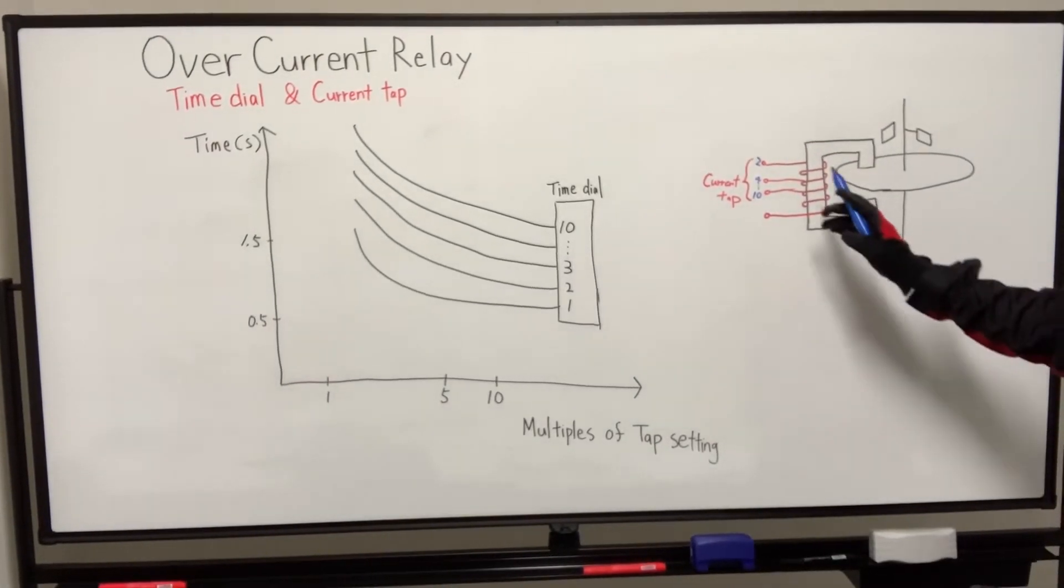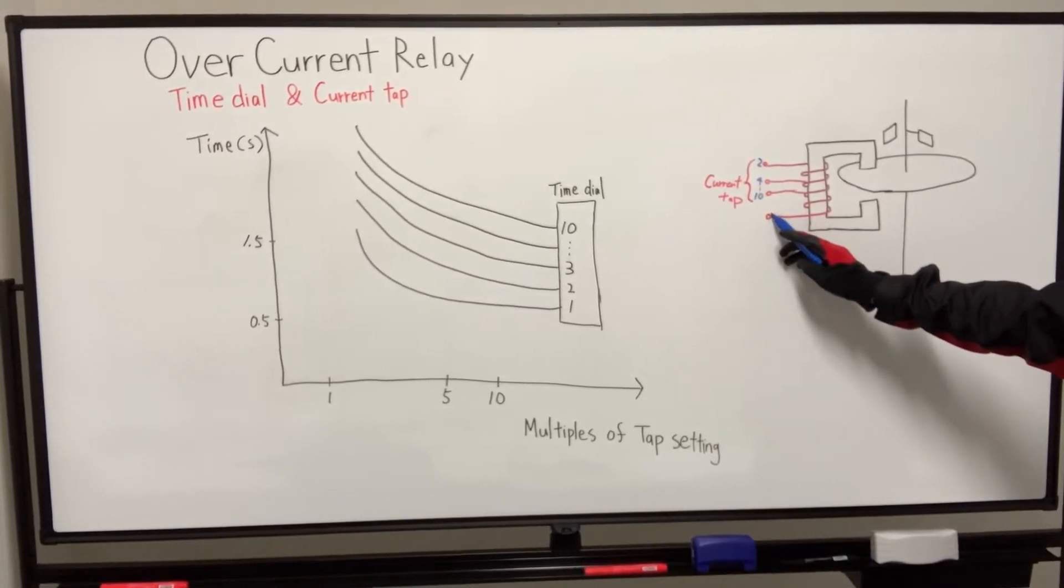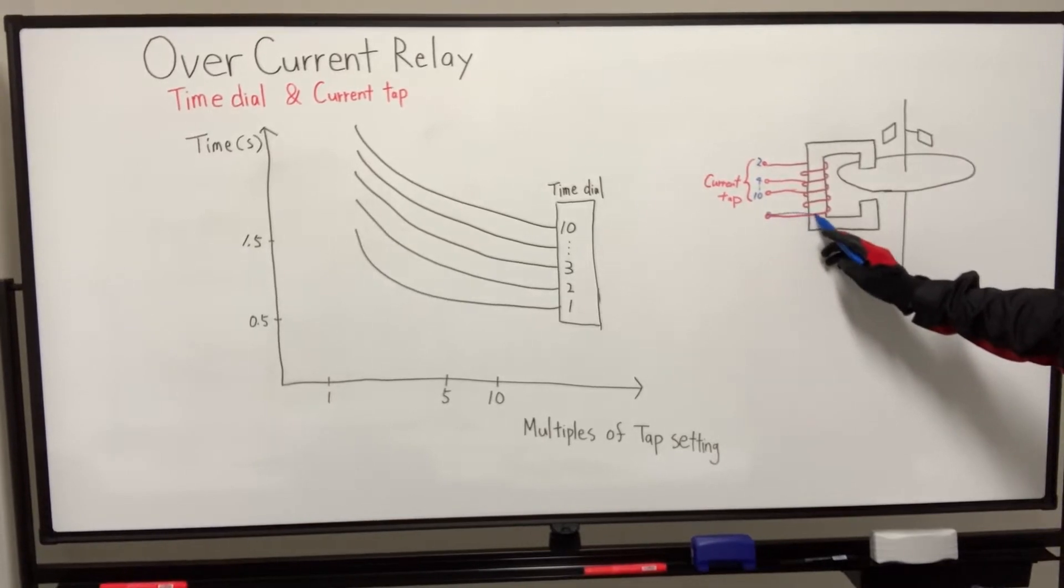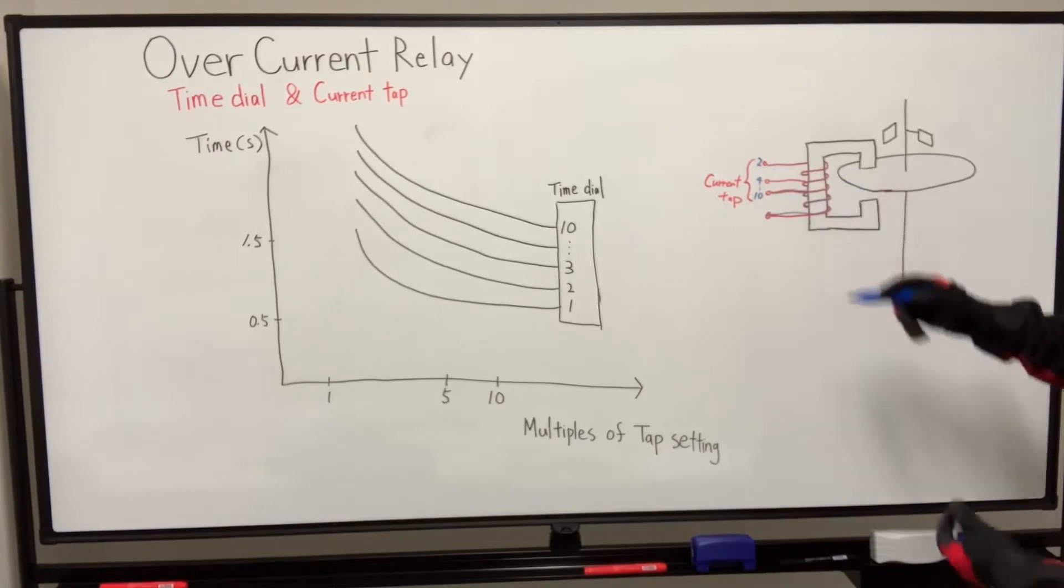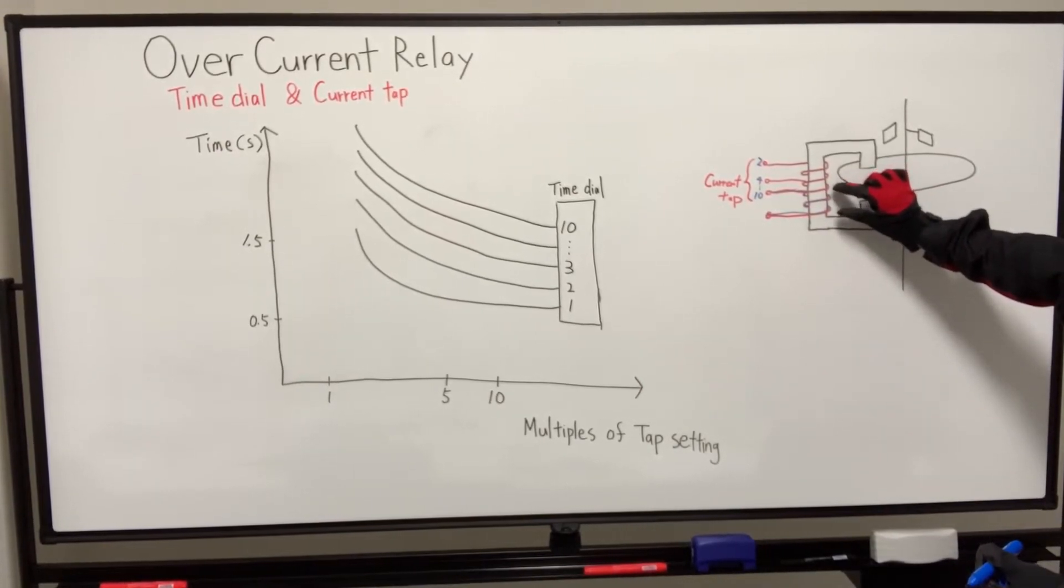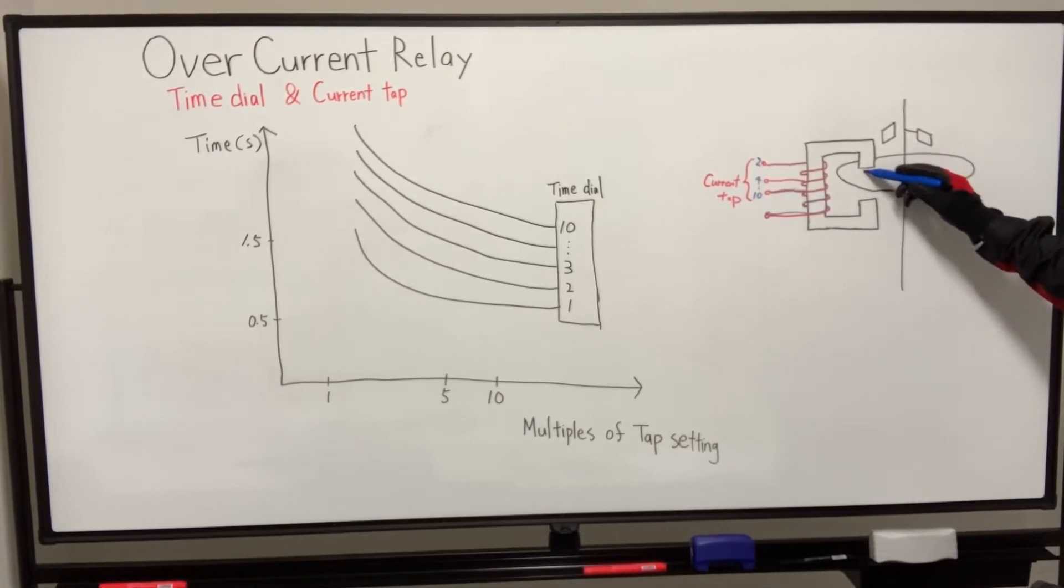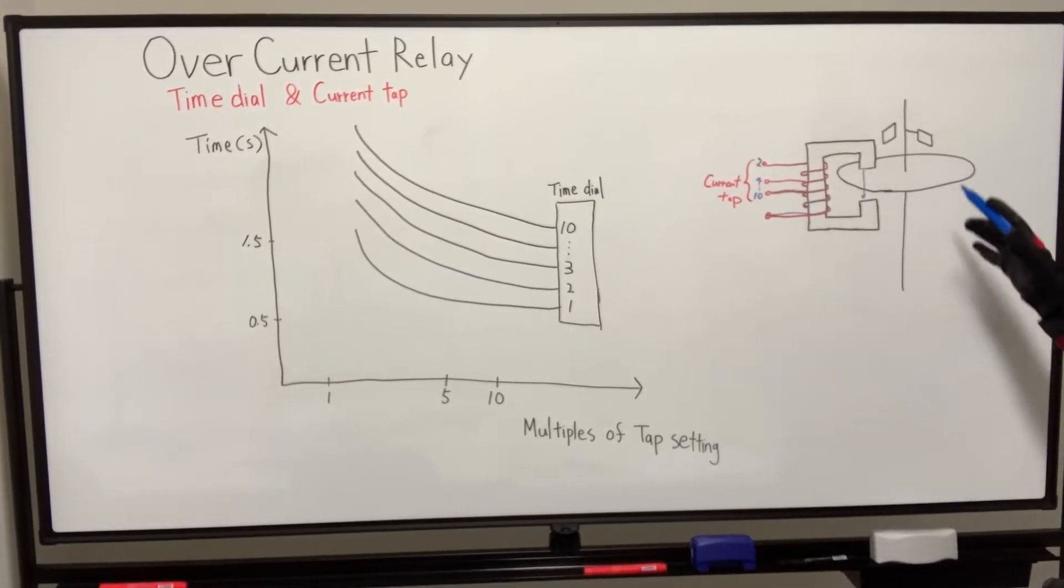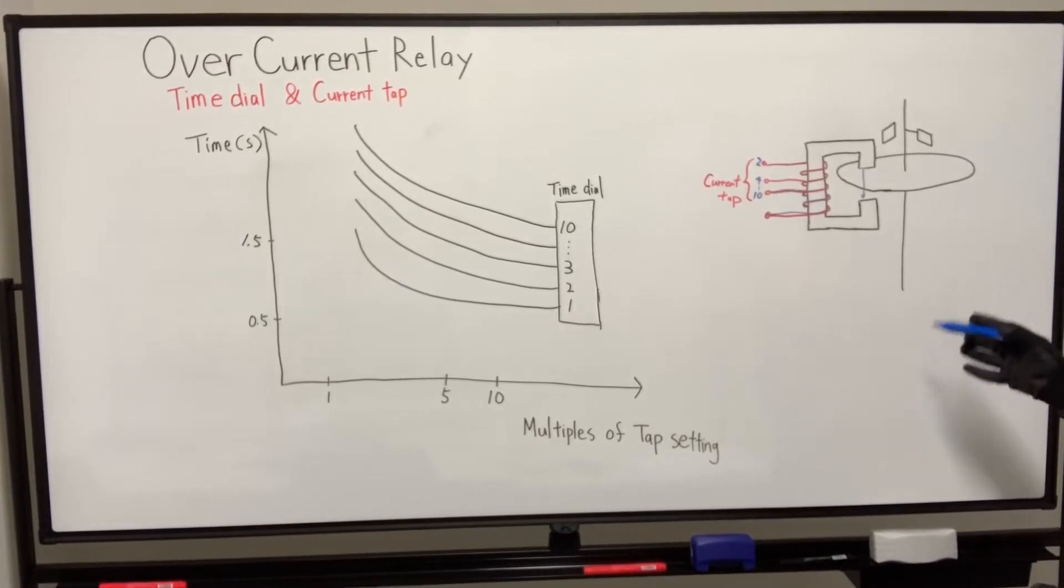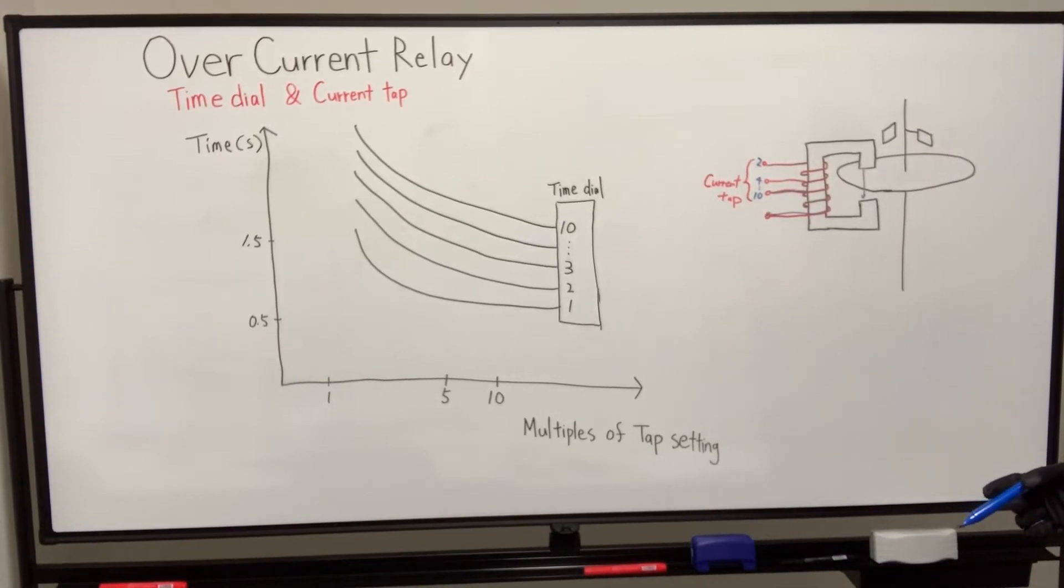On the other hand, if the tap setting is number 10, the distance between fixed and tap is very short. So the shorter coil creates a weaker magnetic field. The disk rotates feebly and takes more time for contact closure.